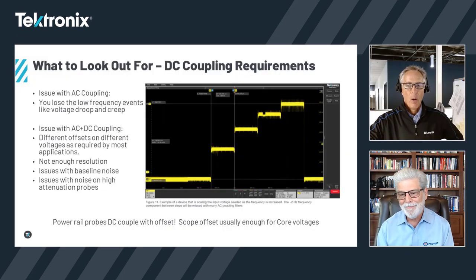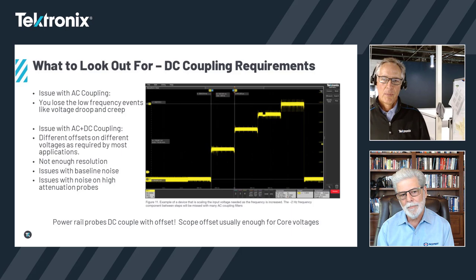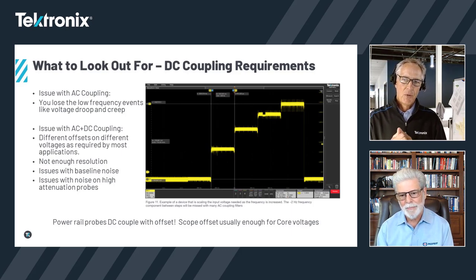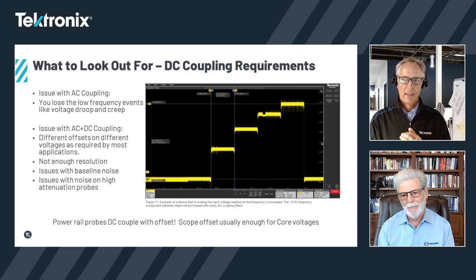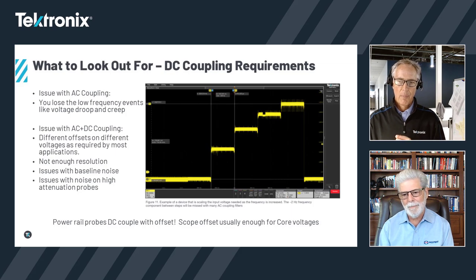One of the other tips to look out for: if you're measuring noise and you really want to understand low frequency events like voltage droop and creep when you're looking at these power rails, make sure you understand the impact that good DC coupling can have on the measurements. Choosing probes that have DC coupling with offset is critical. There's a power rail probe from Tektronix, and Steve at Picotest also has some additional probe help here. But keep an eye on DC coupling requirements for these power rail measurements.